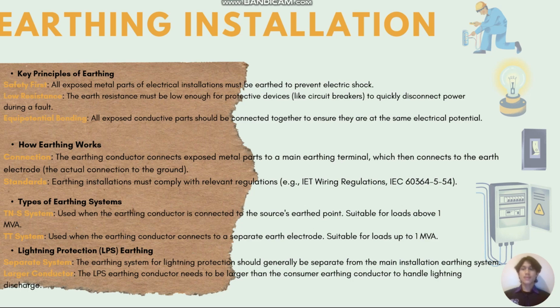Next, we have the types of earthing system. We have the TN-S system and the TT system. The TN-S system is used when the earthing conductor is connected to the source's earth point, suitable for loads above 1 megavolt ampere. The TT system is used when the earthing conductor connects to a separate earth electrode, suitable for loads up to 1 megavolt ampere.